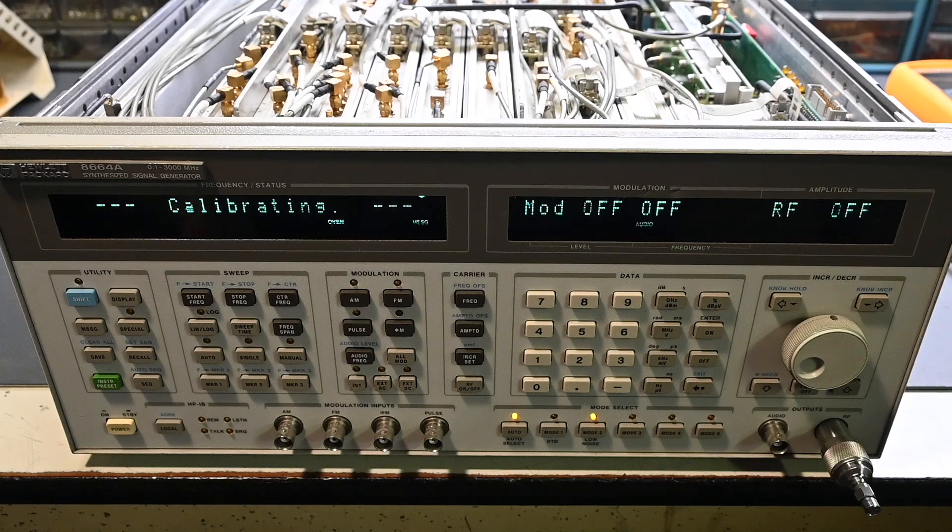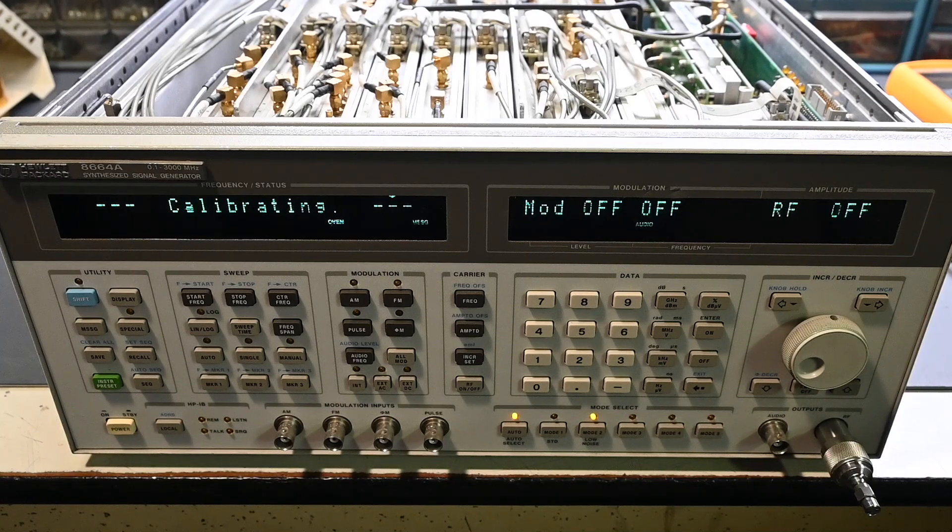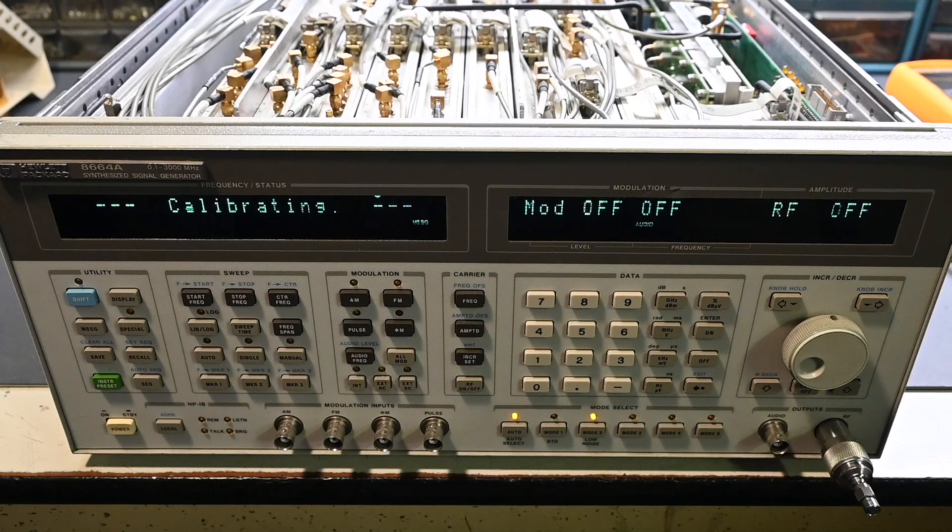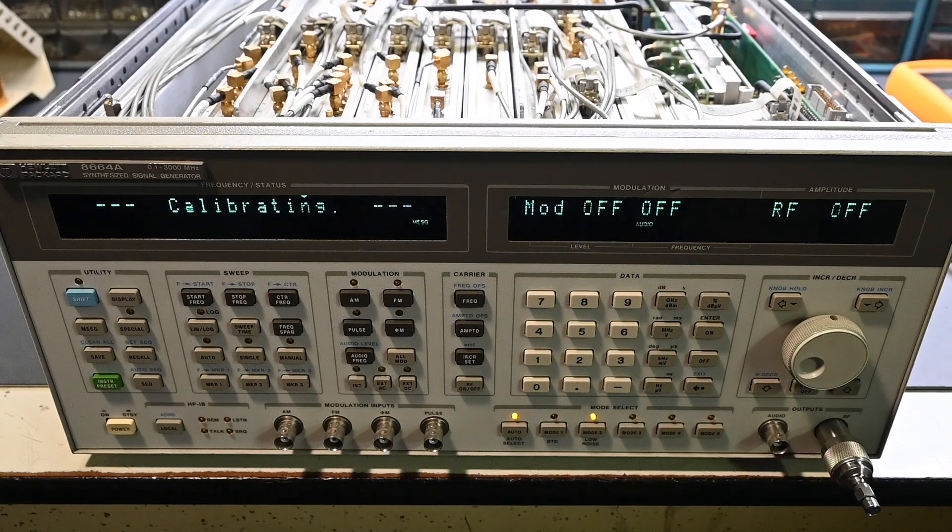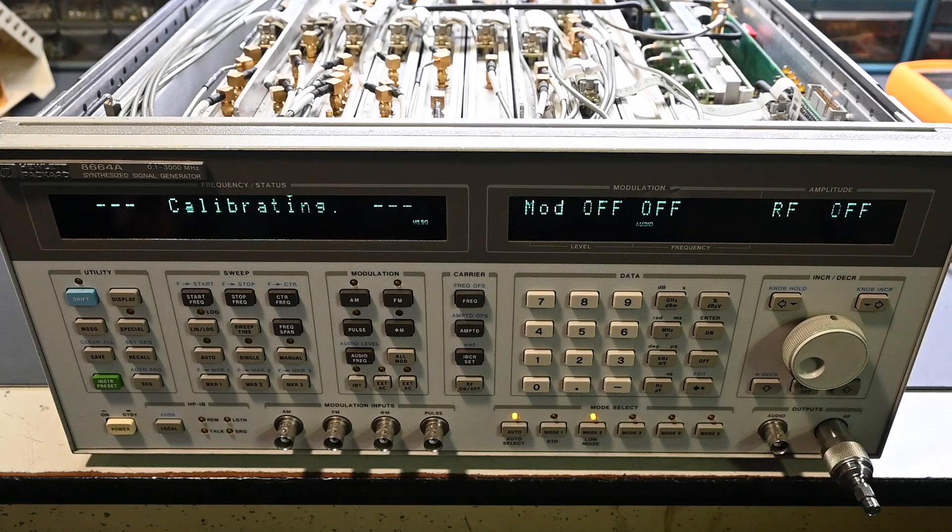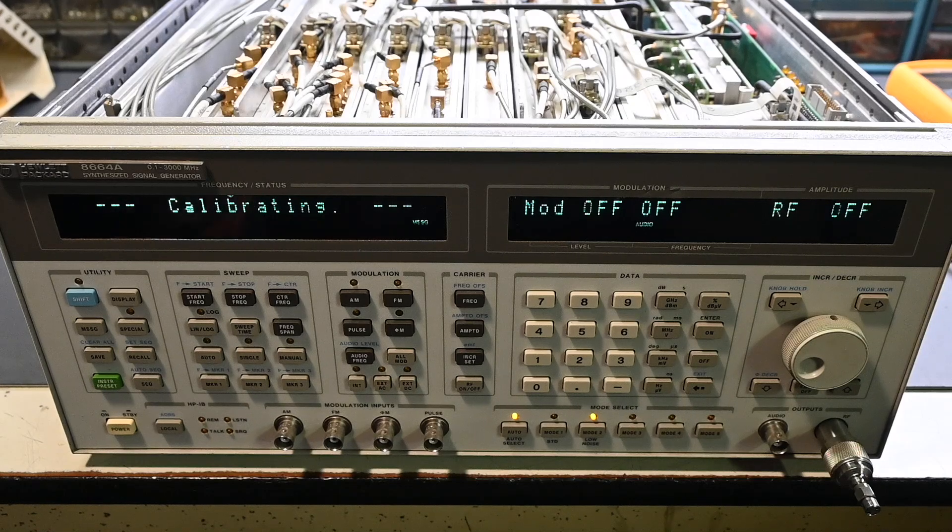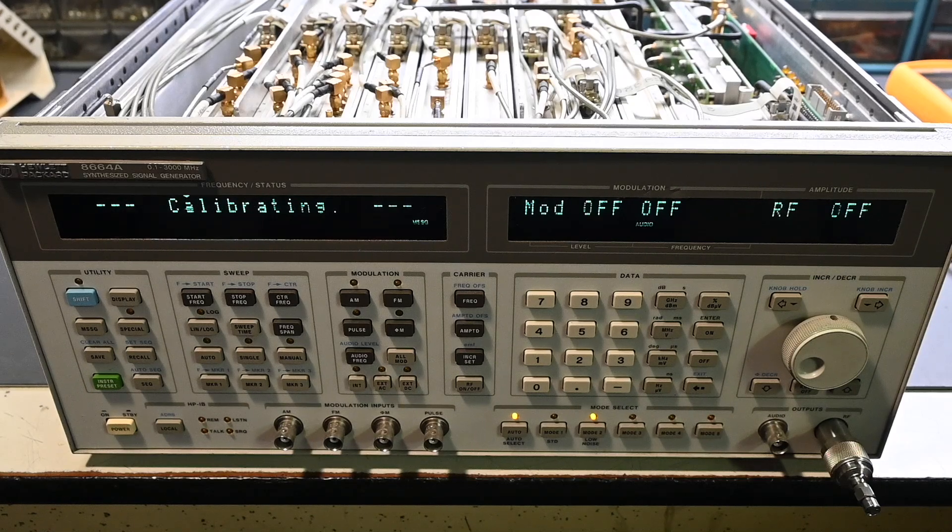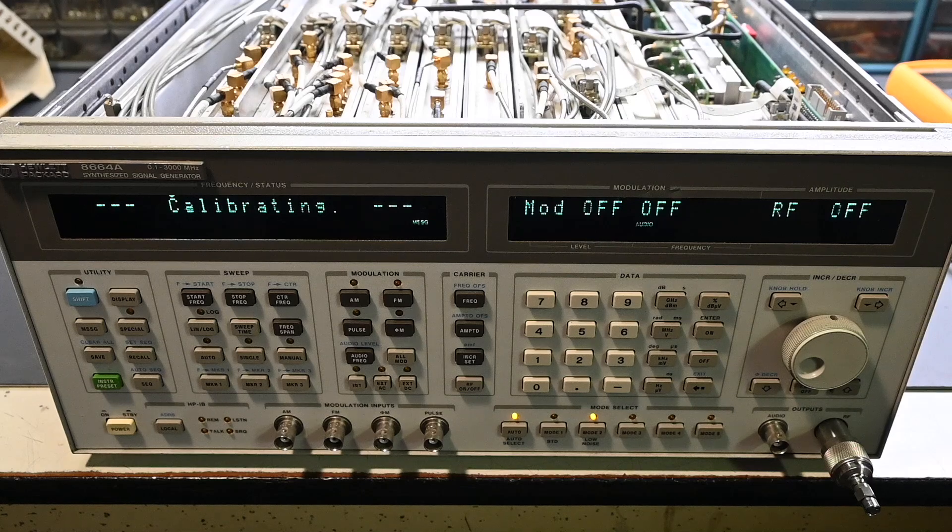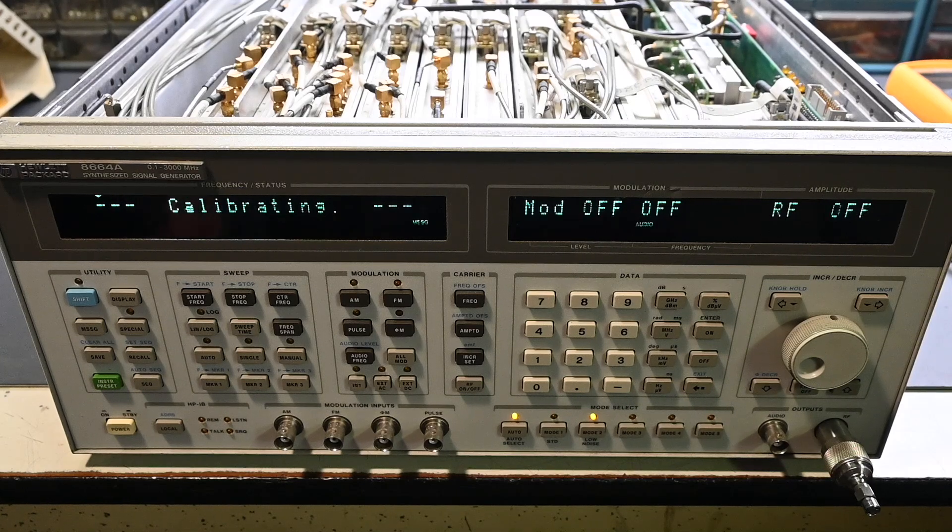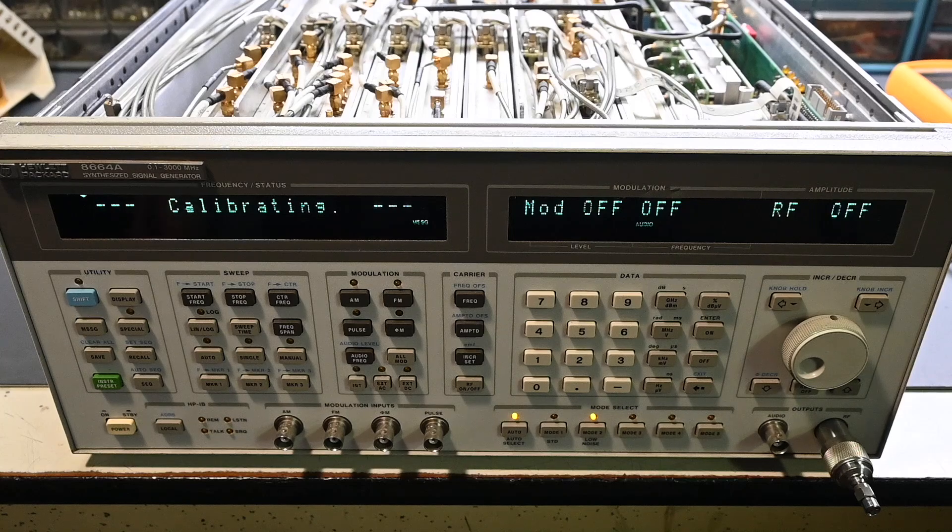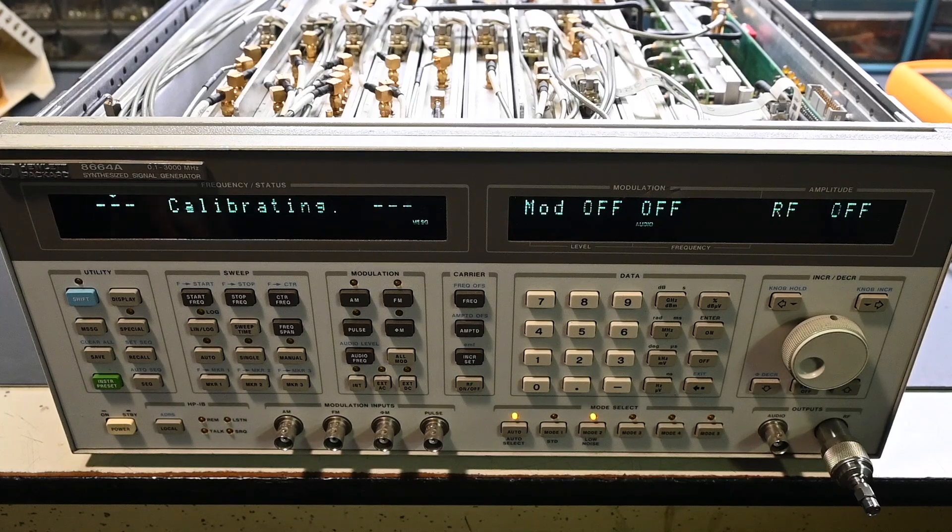And the reason that it has to recalibrate is because the memory holdup battery is on that control board, but the calibration EEPROM is separate, and it's on a different location. So when you remove the control board, the battery goes with it, and it breaks that backup power that's going to the calibration EEPROM. So anyway, here it goes on the calibration, let's see what happens.